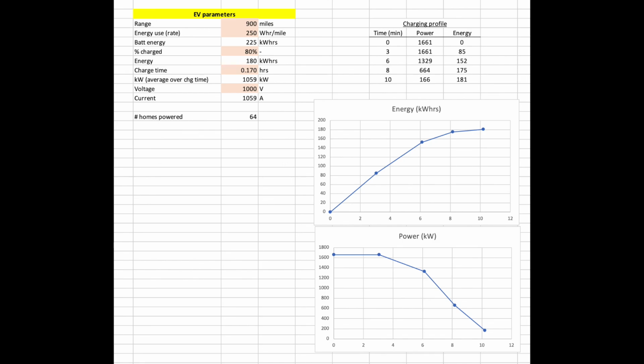Now the current requirement, even at a conservative 1 kilovolt, would require almost 1060 amps. That's a tree trunk of a cable, really. It would require very special switchgear to handle that kind of current, unless they go to much higher voltages, which we haven't seen yet. That's another area to be aware of, where they go with the voltages.